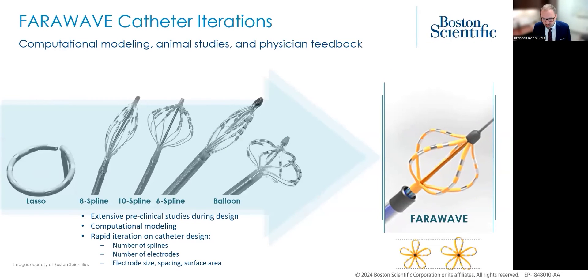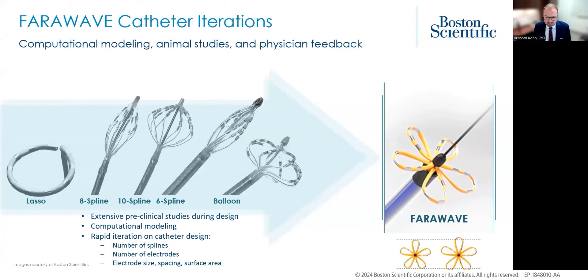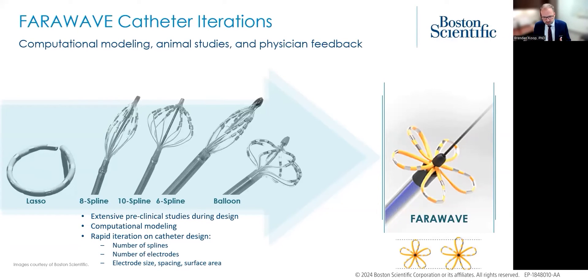The way this was done with FARAWAVE was with extensive preclinical studies during the design, a lot of preclinical studies, computational modeling, and rapid iteration on catheter design, both within Boston Scientific and after bringing in Farapulse. We researched many different catheter designs, including a lasso-type design — with the difficulty that tissue apposition is hard to keep consistent with that form factor, and it's hard to connect crescent-shaped lesion zones. Once we moved to the basket form factor, which is ideal for PFA, we explored eight splines, ten splines, six splines, a version with a balloon, and eventually ended up with the design you see on the right — the FARAWAVE catheter.